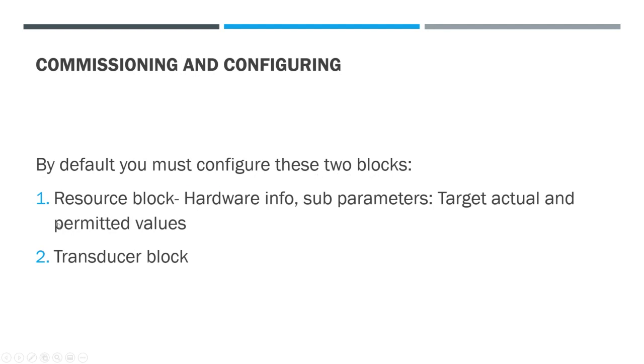The resource block, which contains all the hardware info, sub-parameters such as the target, actual, and permitted values that we're measuring, reading, and writing, and also the transducer block. The transducer block is the one that converts our signal. These two blocks have to be configured, and there's about 7 pages in the ILM that walk you through it. I do encourage you to read it, because it is not dissimilar from doing function block programming in PLC.